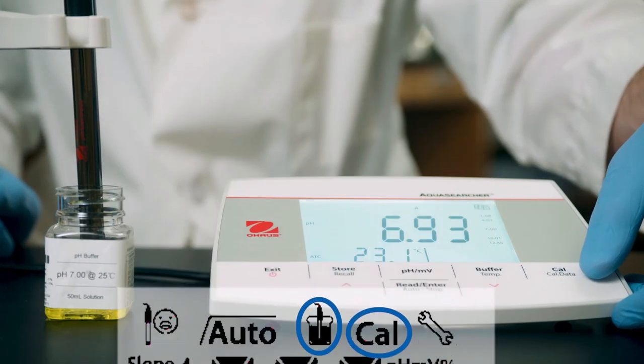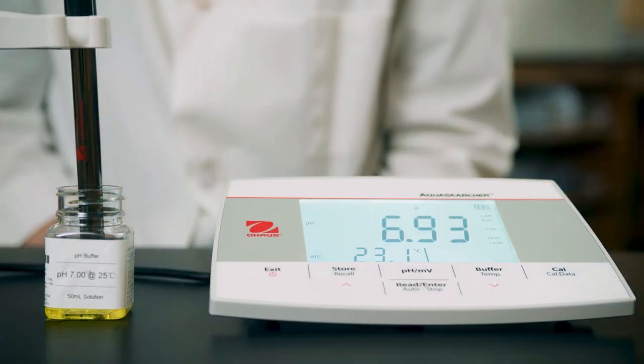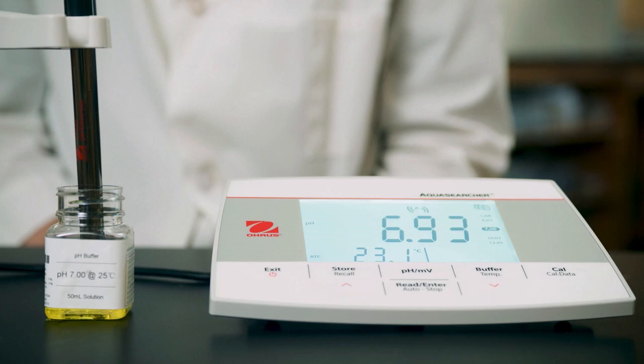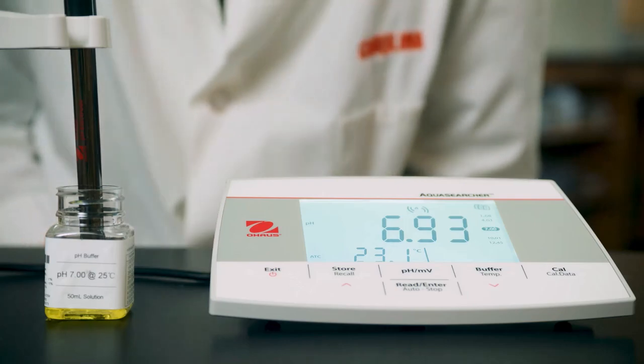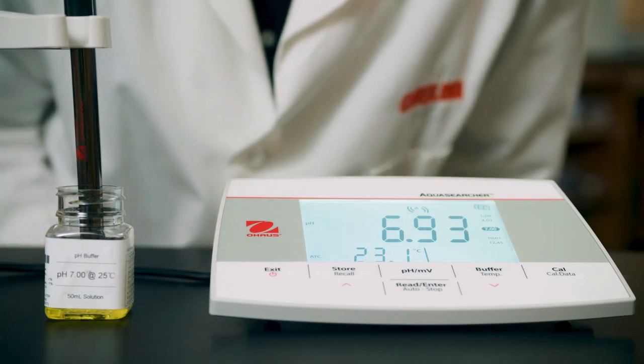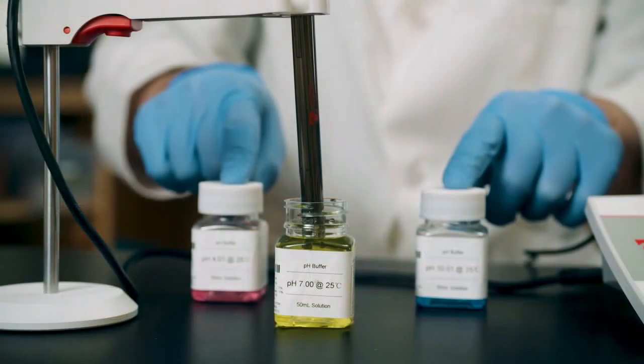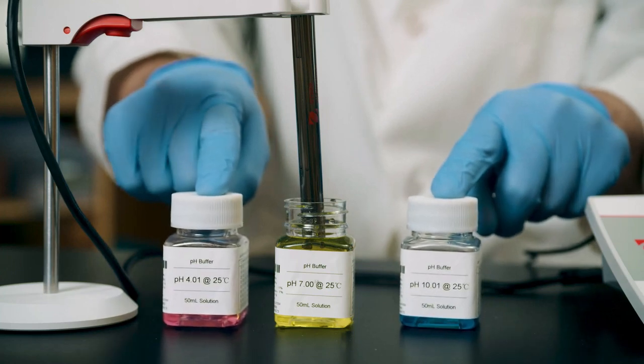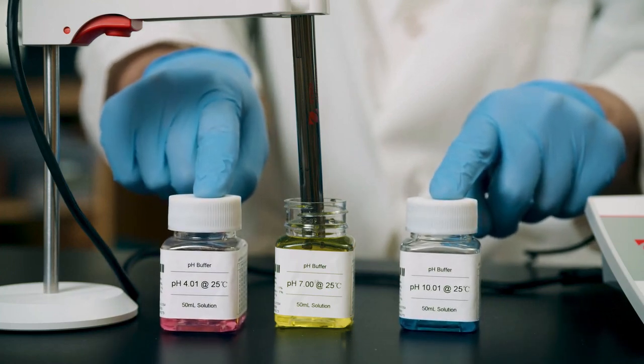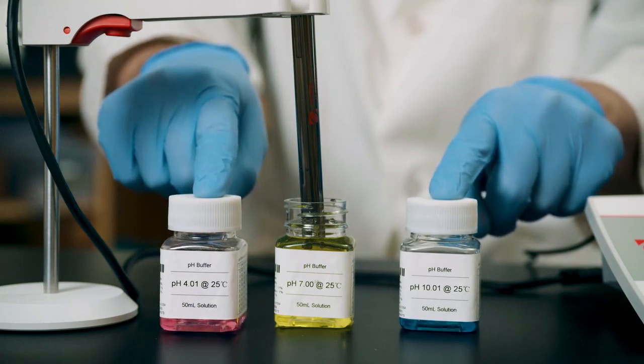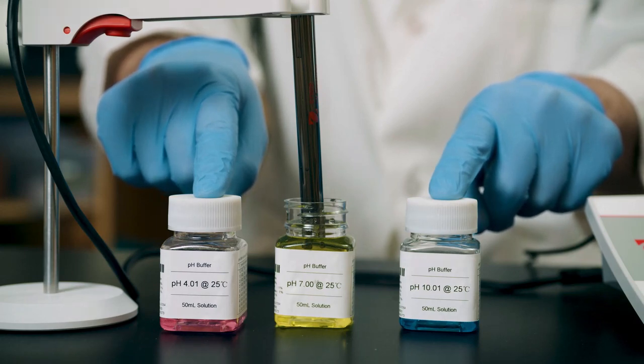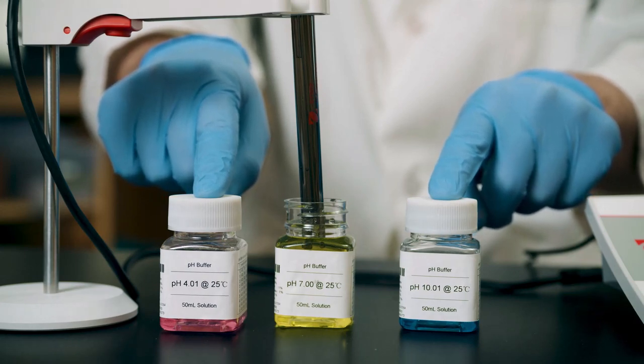During calibration, the measurement icon blinks. When the reading does not change for 5 seconds, the reading is stable. Press the Read Enter button to lock the reading. The bench meter is now calibrated and is ready to be used. Recall that this is a 1-point calibration. Other bench meters may require 2- or 3-point calibrations. To perform these calibrations, repeat the calibration process with additional buffer solutions at different known pH values. Follow your bench meter's instruction manual.